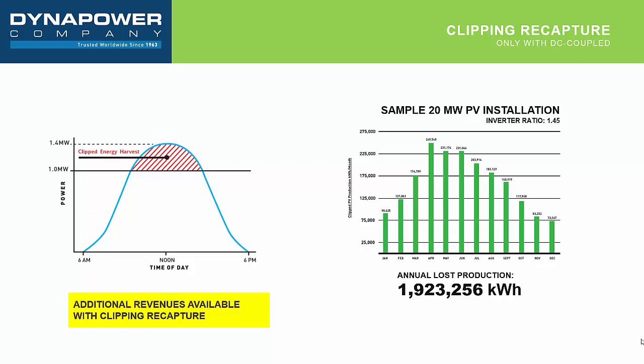So this is lost in an AC coupled storage system because there's no way to push that energy out through your inverter. The inverter, that is the PV inverter, is the bottleneck in the system. So when we go DC coupled, all of a sudden, we can now charge the batteries off that DC grid, capture that excess clipped energy, which would otherwise be lost, and still be able to maximize the output of the PV inverter. So if you do some quick math on this, and again, this is just an example chart from a 20 megawatt array, which happens to be in the Midwest of the US.